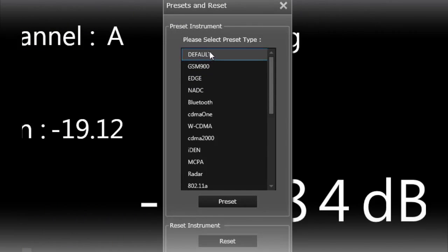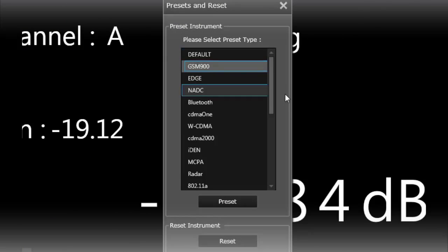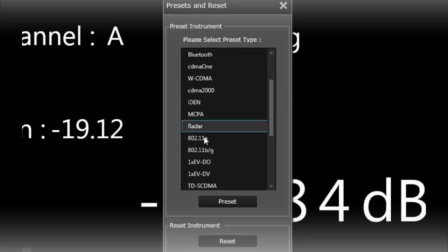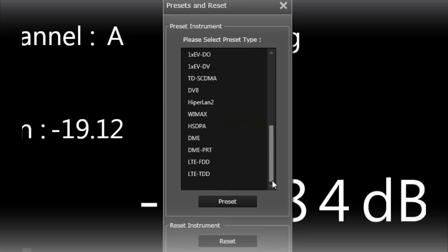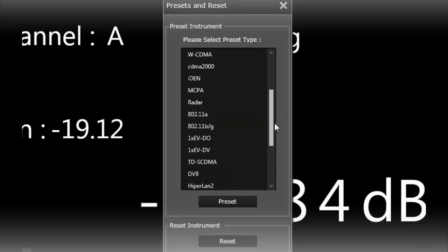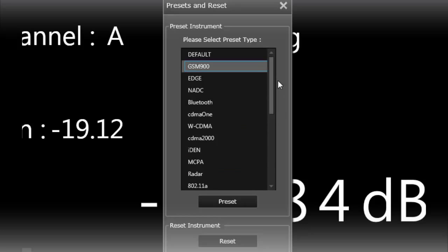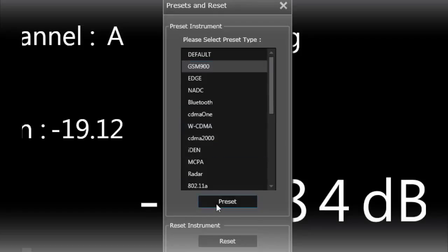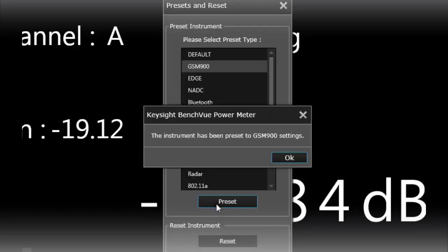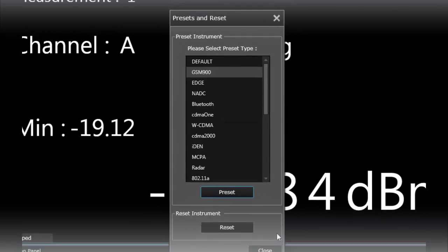And within the presets we have GSM 900 but again you can also do radar type measurements or maybe an LTE preset measurement so that it presets your power sensor to measure those types of modulation signals. So since I have GSM 900 press that preset button to set up my power sensor.